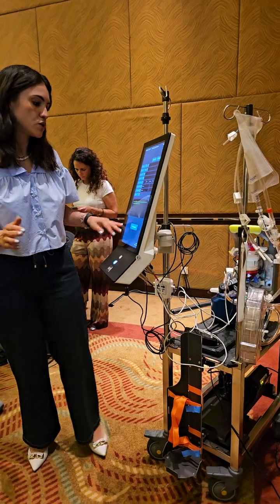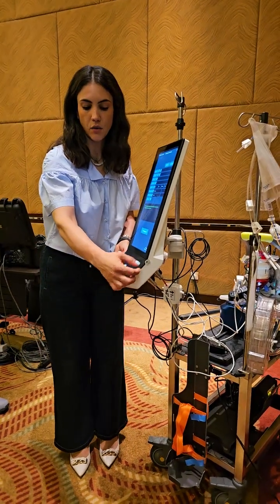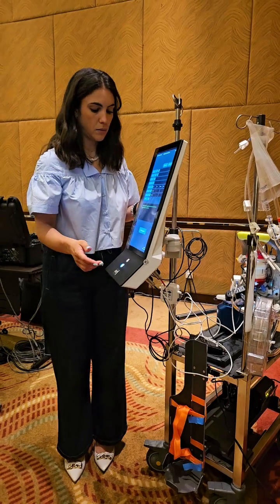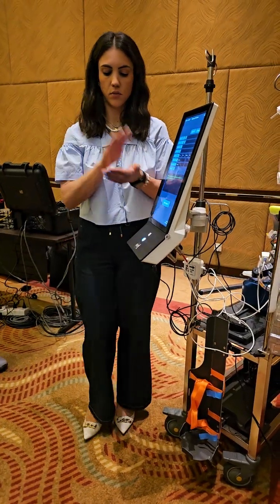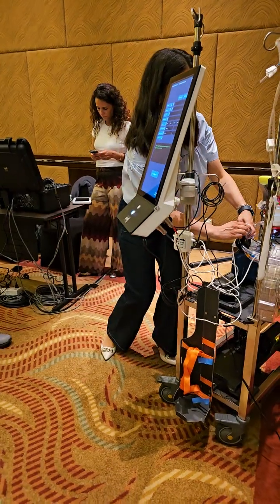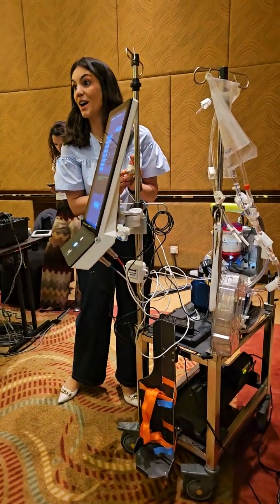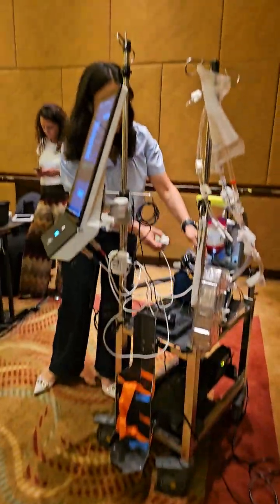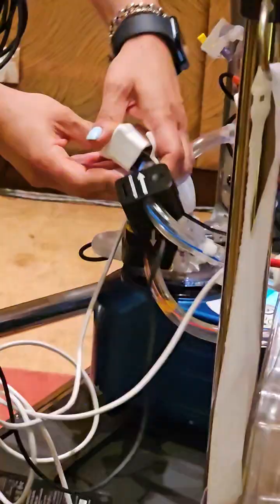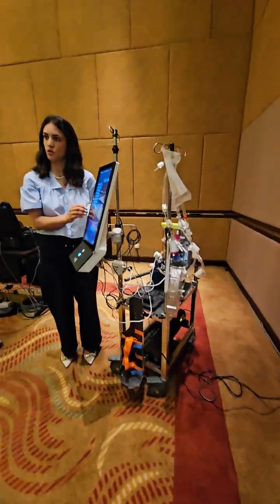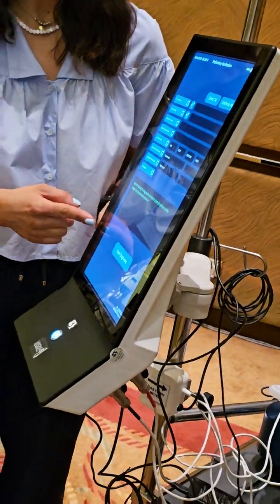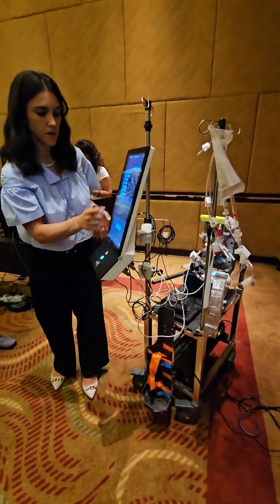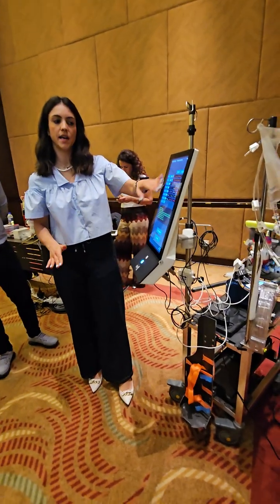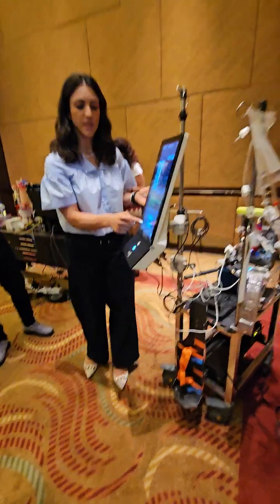So you just have to remember to keep the probes connected on their parking places, or in your hand like this, because the probe has to see dark to be calibrated, but it requires really a few seconds. And the capnometer disconnected, that's all. Capnometer disconnected like this from the oxygenator. So in this way you will perform the diagnostic phase that will require a few seconds. So it will say connected, not connected, and you will be able to continue the procedure.